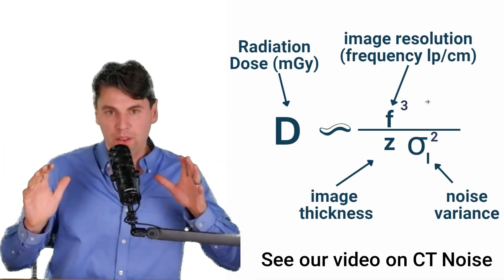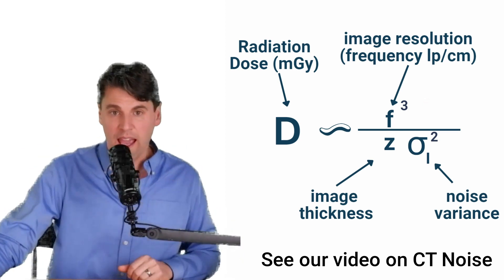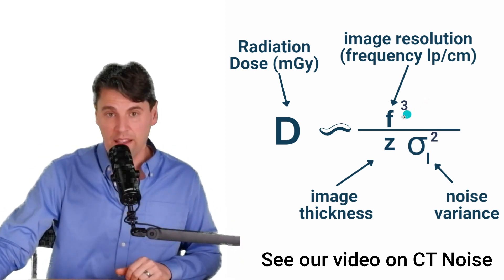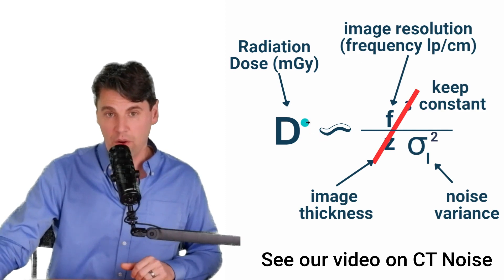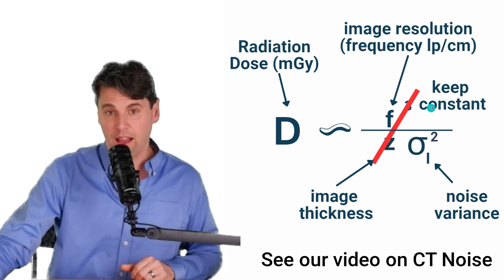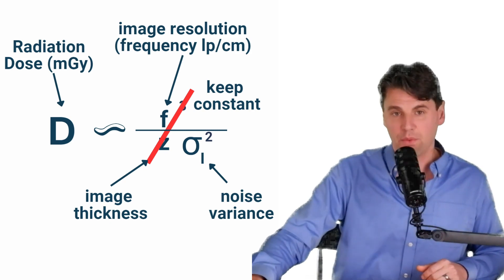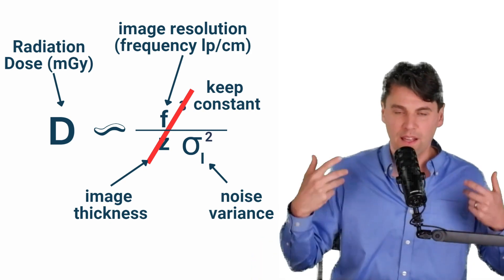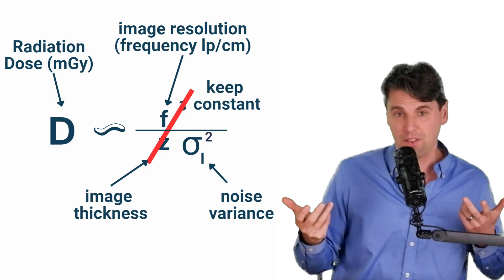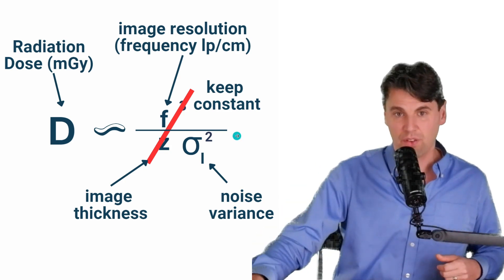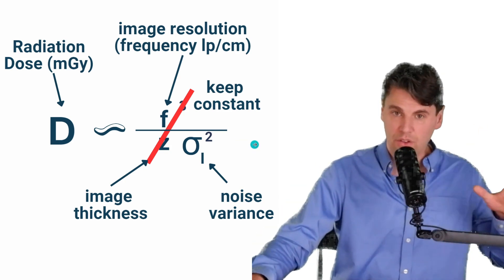If you remember, we talked about the dose in the CT system, and it depended strongly on things like the in-plane spatial resolution, the Z resolution. If we leave those two things constant, though, then the dose actually depends on one over the variance in the image. Remember, variance is actually just the square of the standard deviation. When we talk about noise, a lot of times we're talking about the standard deviation, but the variance is just the square of that. So that's the dose term.